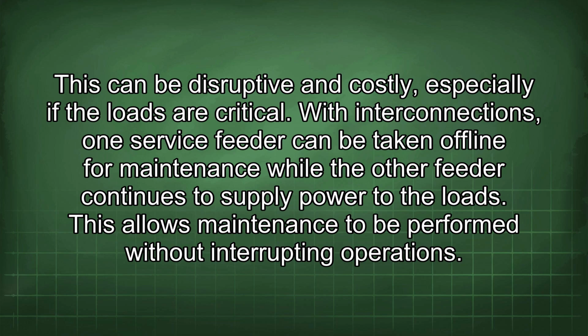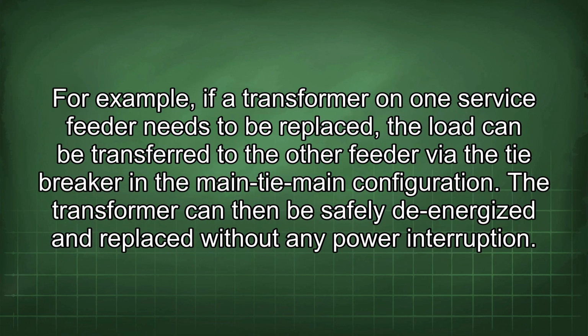With interconnections, one service feeder can be taken offline for maintenance while the other feeder continues to supply power to the loads. This allows maintenance to be performed without interrupting operations. For example, if a transformer on one service feeder needs to be replaced, the load can be transferred to the other feeder via the tiebreaker in the main tie-main configuration. The transformer can then be safely de-energized and replaced without any power interruption.